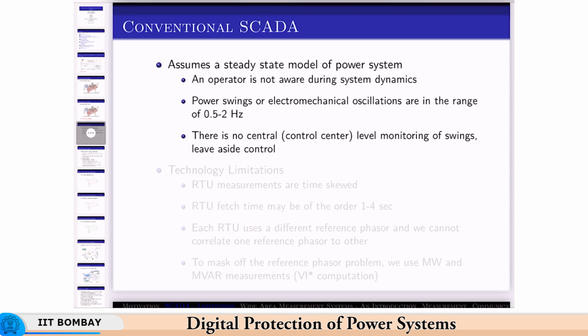If you remember in one of the lectures, we saw the time duration of power swings. Power swings are electromechanical oscillations in the range of about 0.5 to 2 hertz, that is the swing frequency. So with a scanning rate of 1 to 5 seconds, there is no visibility of the swing, so no monitoring.